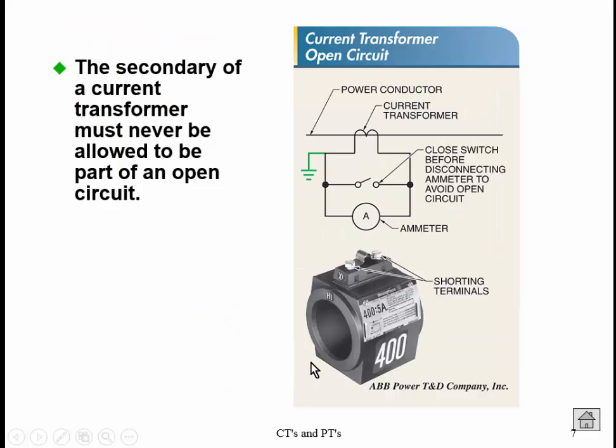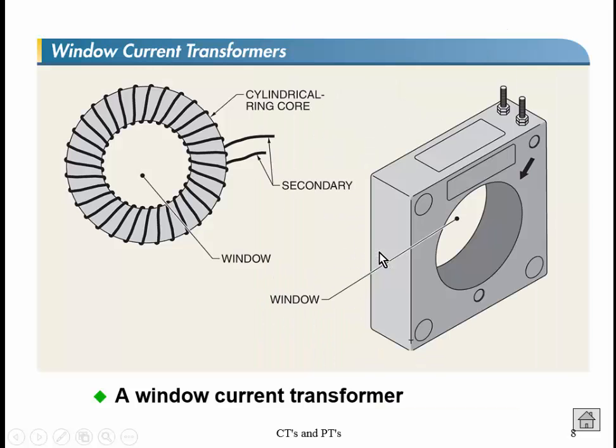So here's a representation of it schematically, a CT, right? You got the little bubble deal, that's the schematic. And notice this already has a shorting switch built in, so we can short this CT and leave it shorted for safety. If we open that switch, now current will flow through, in this case, an amp meter. So that's a nice little depiction of a transformer. Again, the primary, notice this even says H1, the primary, the cable would go through the middle. That's the primary, one turn if you will. And then the secondary are the wraps around the outside that come out X1 and X2. And this would go to your device, a relay or a meter, that sort of thing.